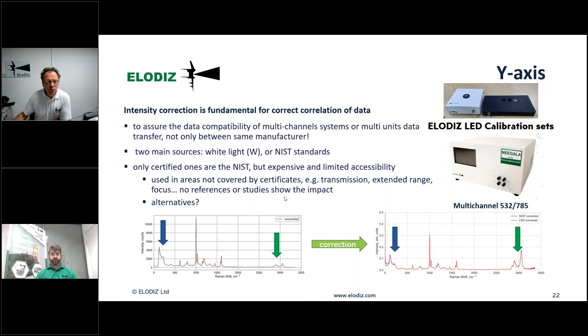Another element that is quite important in the Raman calibration is the y-axis, the intensity correction, the relative intensity correction. More and more nowadays, the intensity correction of Raman is important. Surprisingly, many instruments today are not corrected for intensity. And the problem that we have in those cases is that the response of the system is not homogeneous. So the intensity, particularly in the CH area for the 785 and the low end for the 532, is very heavily affected by the type of instrumentation that we have. And my colleague James Thomson will explain that in the next talk. So we have paid a lot of attention to how to do those intensity corrections.